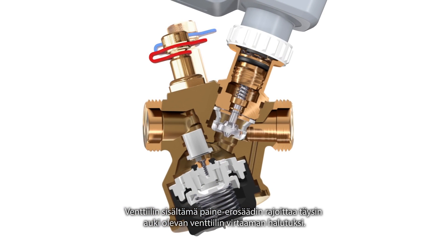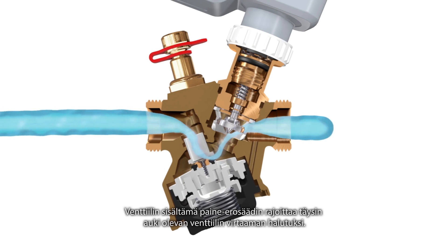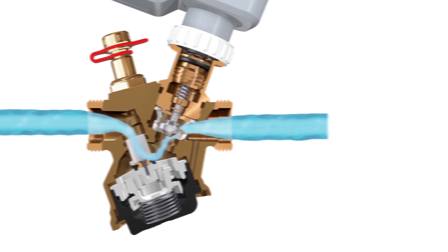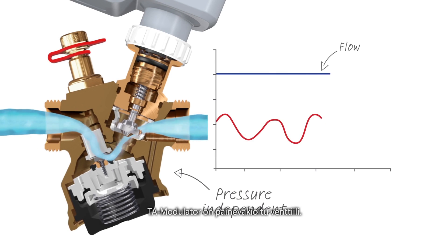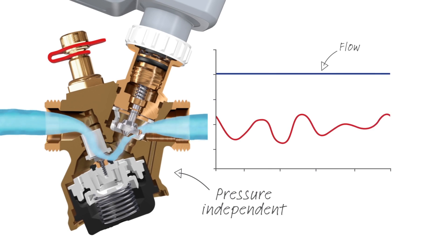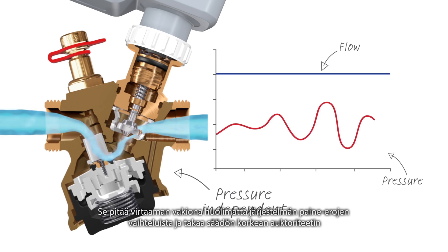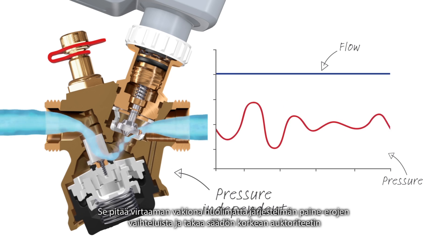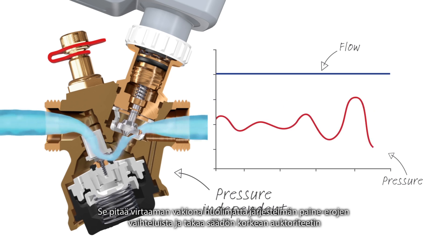The built-in pressure controller limits the maximal flow through the valve when the actuator is fully open. TA modulator is a pressure-independent valve — it keeps the flow constant regardless of pressure fluctuations in the system and guarantees high control authority.